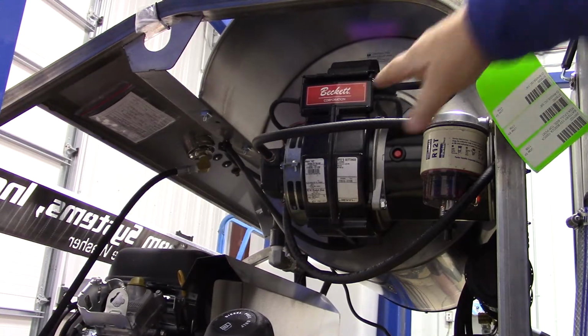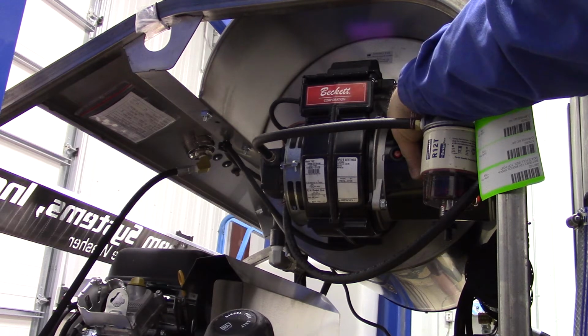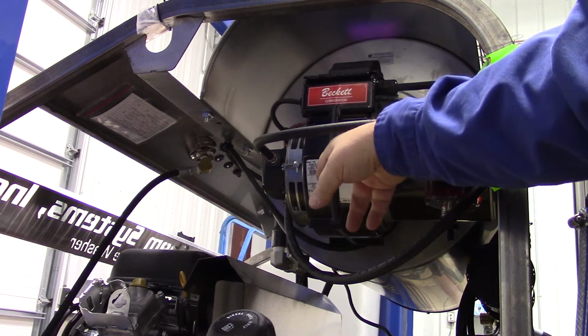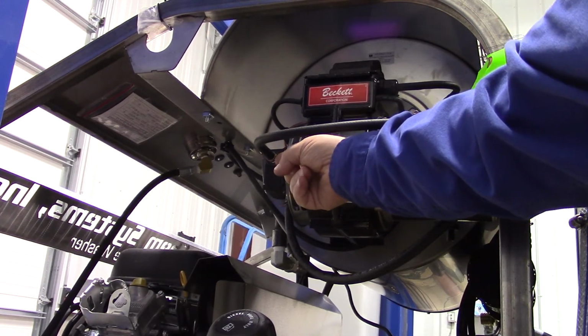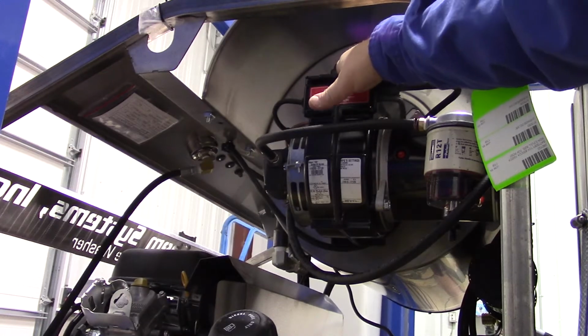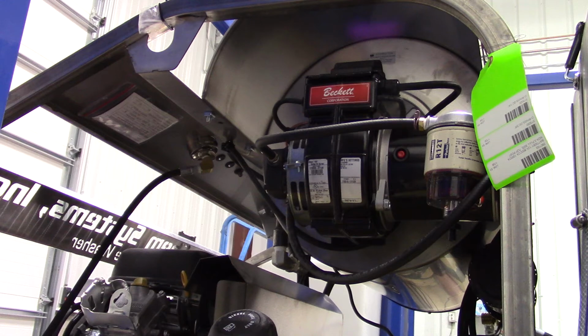This is a Beckett high output, high efficiency burner unit. And it has a blower motor. This is your motor assembly here. Inside here is the squirrel cage, like an air conditioning squirrel cage fan. You've got a fuel pump right here. So the motor is driving the fan. It's got a connector that connects to the fuel pump too. So that does it all. And then you have the electrical spark, which is the igniter system up here. So here's your spark, fuel, and air. And that creates the flamethrower, and that's blowing into the heating coil. Okay. All right.